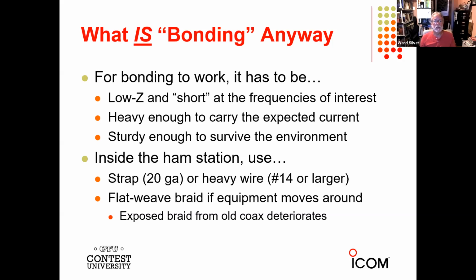If we're talking about AC safety, where there might be short circuits connected to a branch circuit, where you might have a couple hundred, 300 amps for a short period of time, the idea is that you want the bonding to be heavy enough to carry that until the protective components remove the power from the circuit. If you're talking about lightning, then you have to be really heavy because we're talking about kiloamps. I don't know about you, but the concept of kiloamps is a little intimidating, and you want to make sure that the wire or the strap or whatever, the pipe, the bus bar is big enough to carry the expected current. That's especially true when you're outside working on your tower or antenna system. And it has to be sturdy enough to survive in the environment.